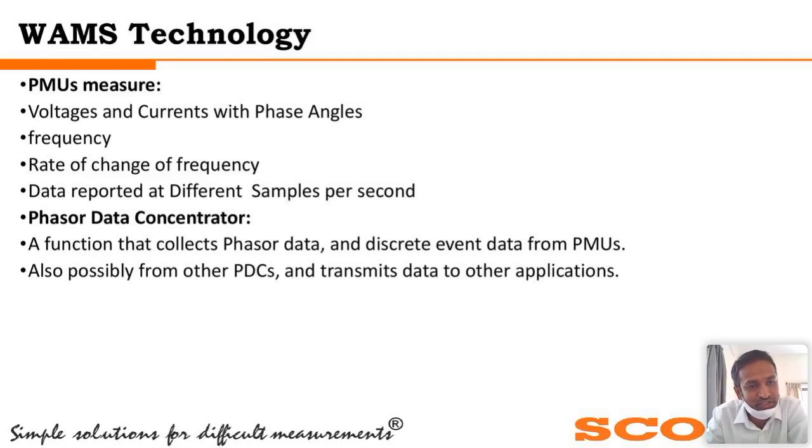And what the phasor data concentrator exactly does is collect the phasor data from the different PMUs, and also possibly from other PDCs. You can even interconnect one PDC with another PDC, and it will take the data from the other PDC, store it, and transmit data to other applications. This is what we call precisely the PDC.